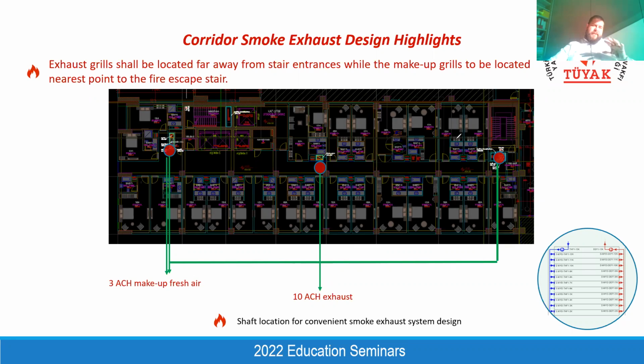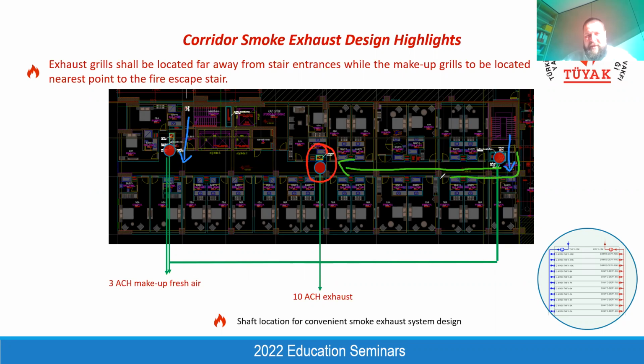you are trying to keep the exit access clear of smoke. That's why we are always locating the makeup grills just next to the staircase. I will make it blue. We provide fresh air just next to the staircases. And we always locate the exhaust shafts as far as possible from the staircases, so that when we have a fire, the air movement will be like that. The air will come from the fresh air shaft, and they will go to the exhaust shaft, so that we will accumulate the smoke far from the staircases, and the entrance of the staircases will always be kept smoke-free.